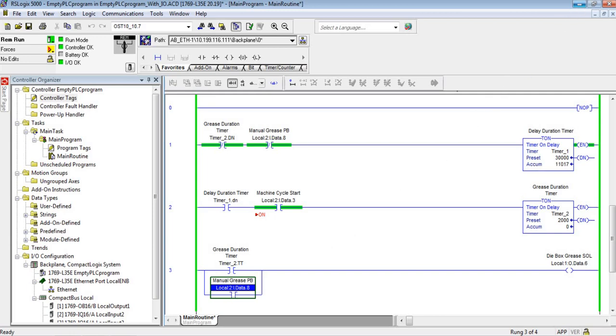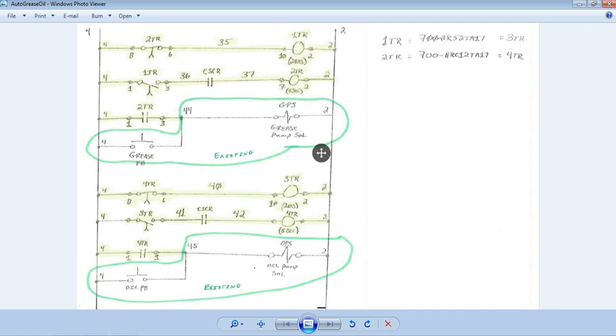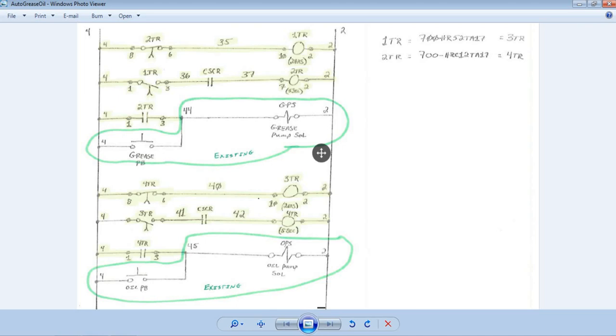In a machine I have out there right now, I have this scenario twice - the grease and the oil. So with the PLC I showed you, I have two timers, a couple internal contacts from the inputs - no big deal at all. Well, this is all really wired. You can see the wire numbers, terminal numbers, the part numbers for the relays. I need to buy two of this relay, two of this relay because those are timing relays - they're the timer instructions in the mechanical world.